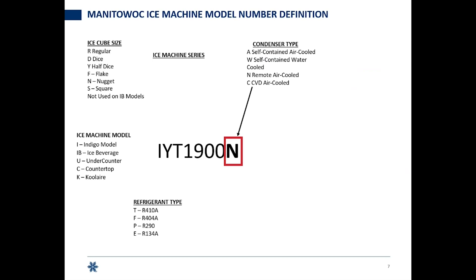That means that the condenser and the condenser fan motor are outside of the ice machine head, so the heat rejection is outside of the ice machine. We do have other options: A for self-contained air-cooled, W for self-contained water-cooled, and C for our CVD air-cooled — systems that have the compressor and the condenser outside of the ice machine head.